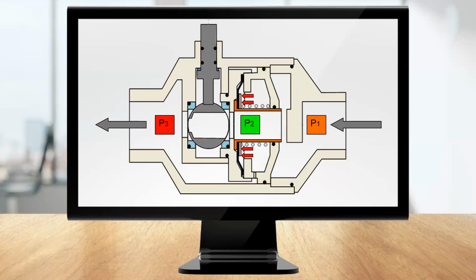Force from P3 pushes the regulator open. Force from P2 pushes the regulator closed. What that results in is the regulator continually moving back and forth, creating that constant pressure across the ball. So as the inlet pressure P1 increases, so will P2, and the force generated by P2 will cause the spring to compress and the regulator to squeeze more closed. The smaller area to push the water through will create a bigger pressure drop between P1 and P2, which will keep the pressure drop between P2 and P3 constant.